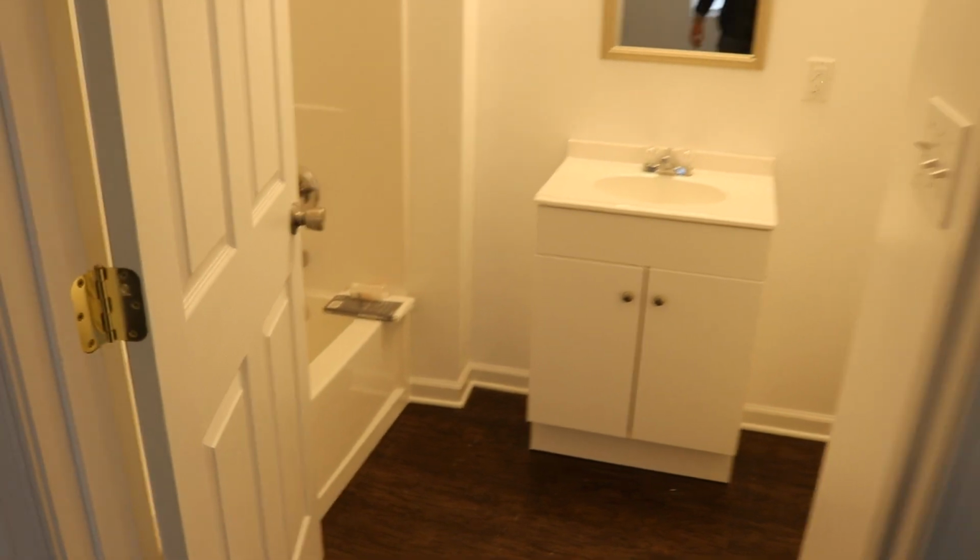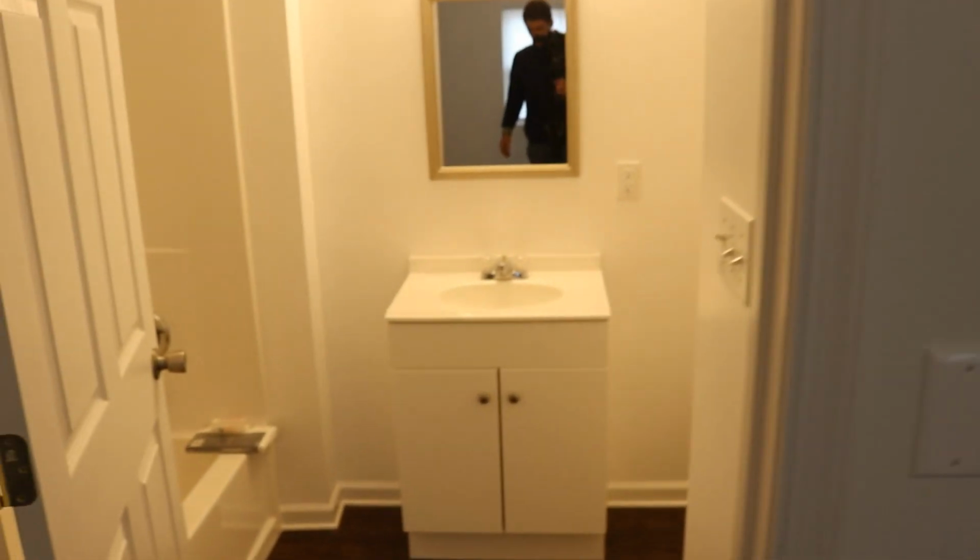So it's not going to cause a fire, but since the packaging on the unit that I bought did not specifically say that it was a zero clearance light, they couldn't allow me to use it. So I just removed it all, put blank covers on here and here, and it's wire nutted off and taped. That was how they said that I could resolve it and it'd be fine.